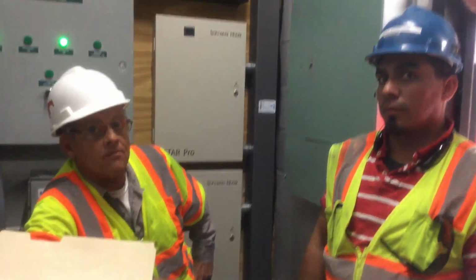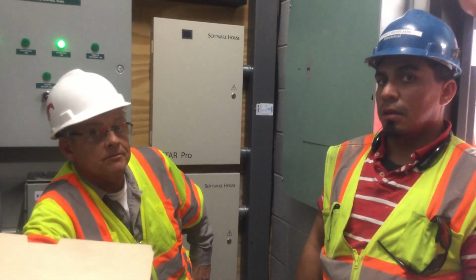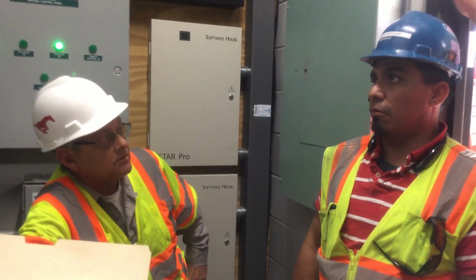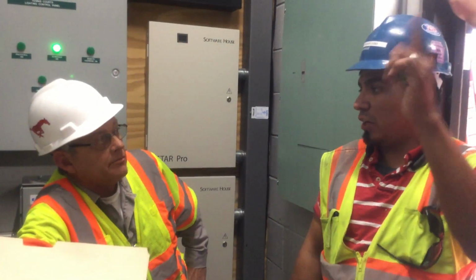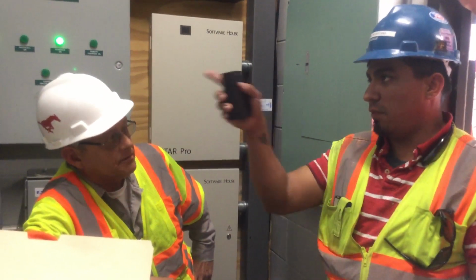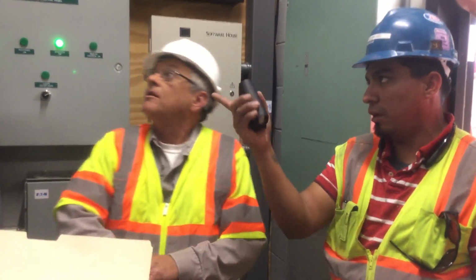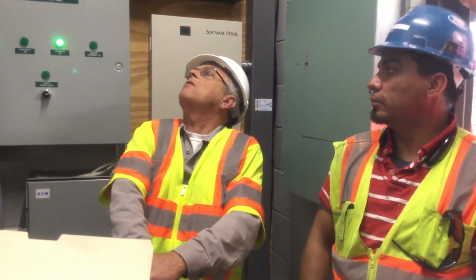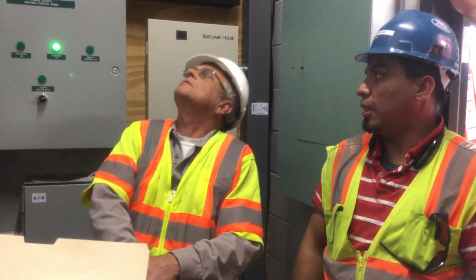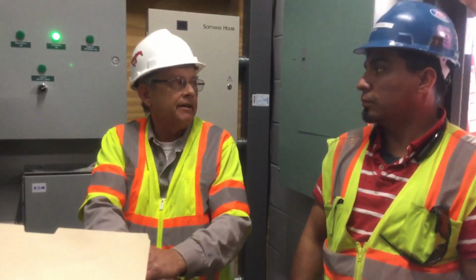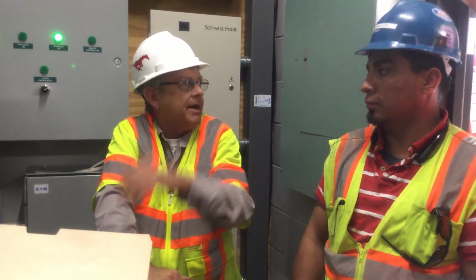Because on the one line diagram, everything just starts at the transformer, right? There's emergency lighting throughout the building, but it's fed off of this panel, and it's not an emergency panel. The reason I'm saying that, I don't think there's battery backup there, it's just emergency lighting, like a 90-minute emergency ballast, that's all it is.